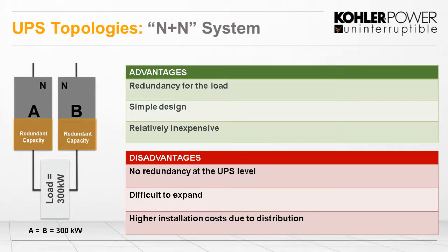So the advantages of N plus N are that we now have redundancy at the load. We can lose either side completely and the load is still protected. As far as UPS design goes, it's quite simple. We just put two complete installations in. So for the UPSs, it's relatively inexpensive. Disadvantages, obviously, if one UPS does go down on one side, there is no protection for that side. Again, if not put in and designed right, it can be difficult to expand. And now we have much more installation here. We have two distribution networks throughout the setup, so the installation cost will be higher for that reason.